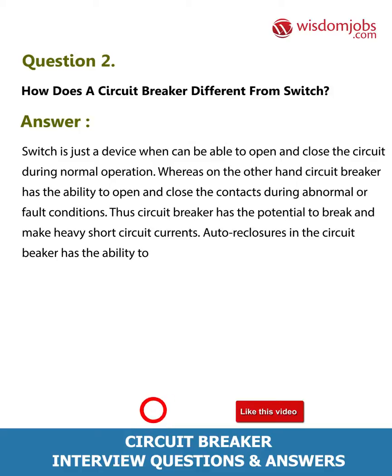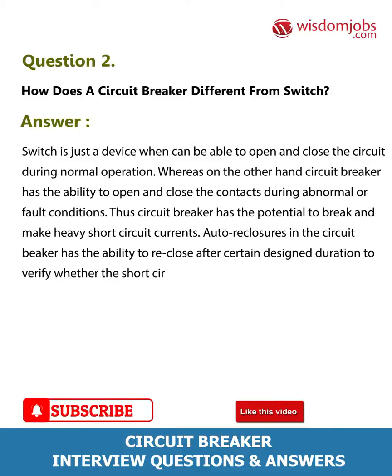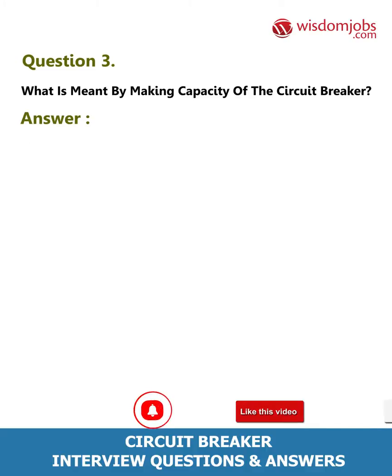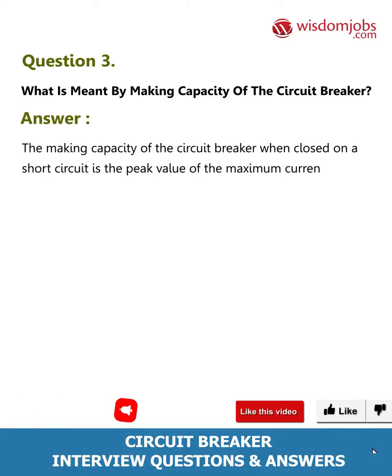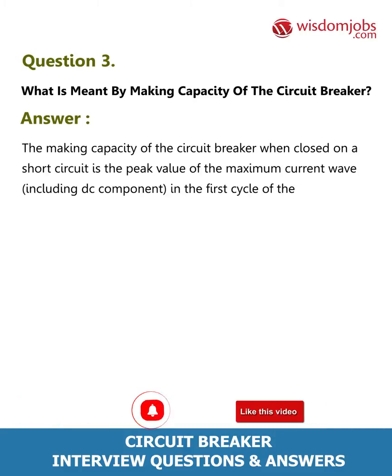The circuit breaker also has auto-reclosure ability — it can reclose after a certain design duration to verify whether the short circuit was cleared. Question 3: What is meant by the making capacity of a circuit breaker? Answer: The making capacity of the circuit breaker, when closed on a short circuit, is the peak value of the maximum current wave including the DC component in the first cycle of current after the circuit is closed.